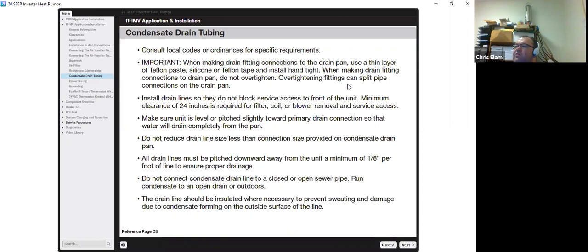Install the drain lines so they do not block access to the front of the unit. Also make sure they don't block the access to the filter. Minimum clearance of 24 inches is required for filter, coil, and blower access. Make sure the unit is level, preferably pitched slightly forward towards the drain connection that is being used. Also, it's important not to reduce the drain size smaller than the connection provided.